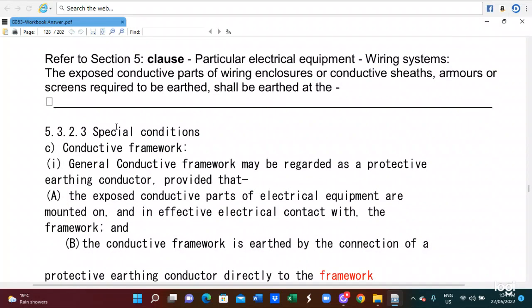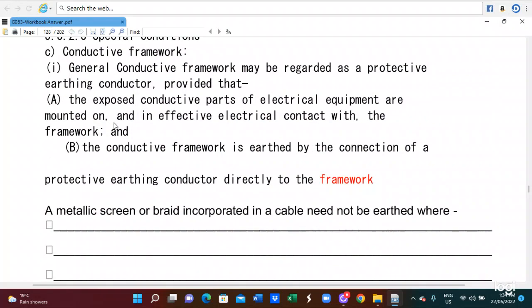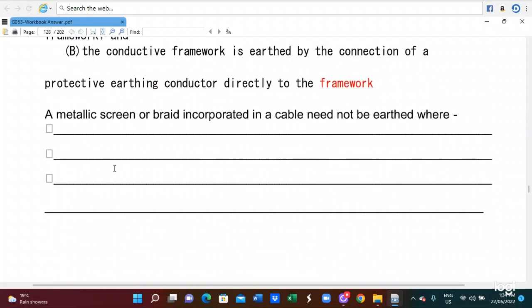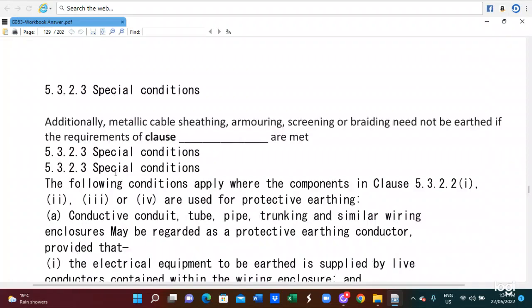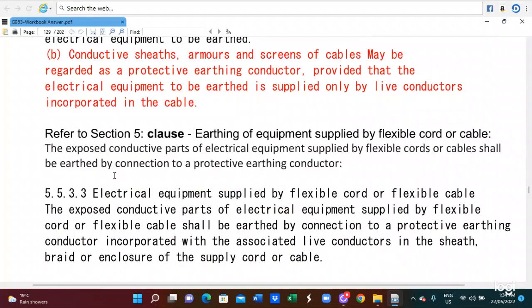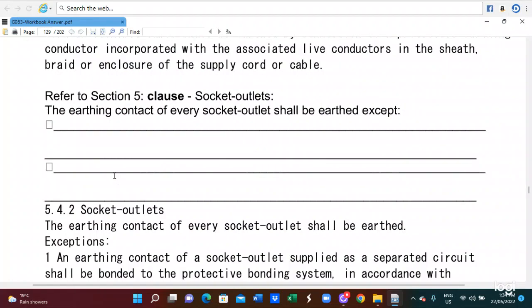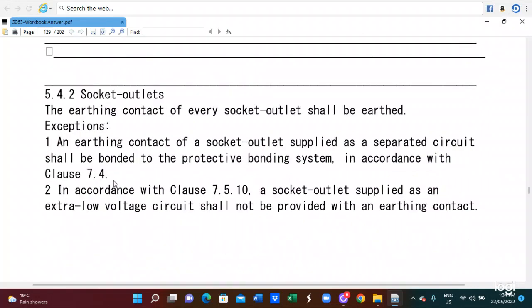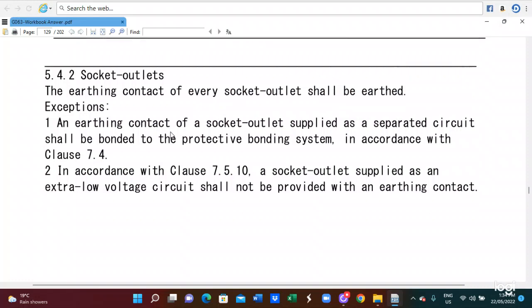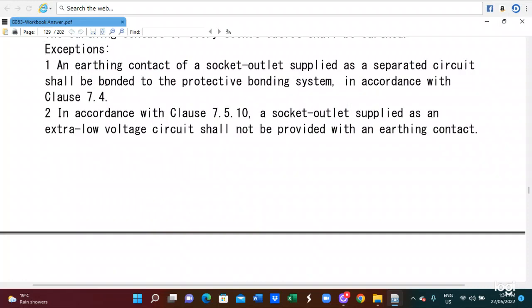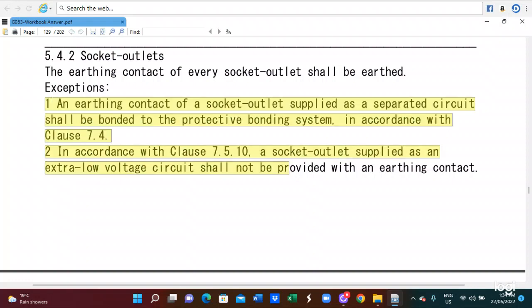And 5.3.2.3 is a special condition. You also read it. So up to this stage, we're talking about the special condition and the conductive part, protected earthing system. And 5.4.2, you can read about the socket outlet. So the earthing contact for every socket outlet shall be earthed. So there are exceptions, exception 1 and 2. You can see that the same.